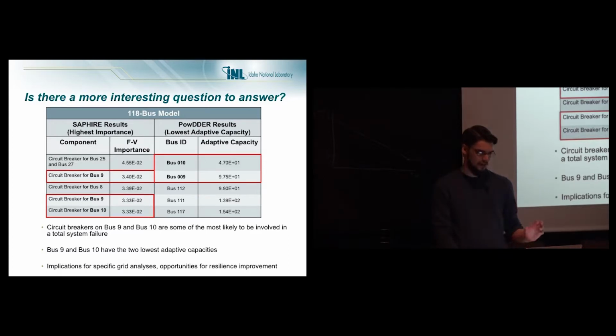What we find is components that are most likely to lead to system-wide failure are in the top 5. We have 2 circuit breakers on bus 9 and a circuit breaker on bus 10, so those are the most likely that if they fail, they're going to lead to system-wide failure. We also find that buses 9 and 10 have the lowest adaptive capacity. So what this means is small voltage instabilities for buses 9 and 10 can cause the bus to fail—a small voltage instability could cause the circuit breakers to trip.